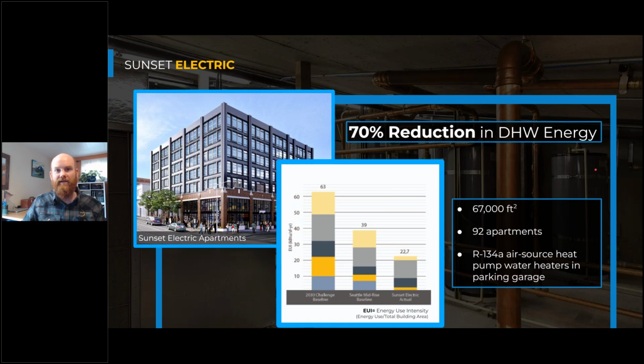And we put it in the parking garage because the R134A refrigerant doesn't perform well under about 40 degrees Fahrenheit. And in Seattle, it gets cooler than 40 degrees. But if you put it in an enclosed underground parking garage, we're creating a buffer zone for that air. And so that air, even when it's drawn into that garage at about 23 degrees on a cold day in Seattle, by the time it gets down to the basement level of the parking garage, the air is warm enough for those heat pump water heaters to extract the heat out of it. It's above that 40-degree threshold. We're getting a lot of great geothermal ground contact with those concrete walls that are uninsulated. There's a lot of thermal mass down there. So it's a really simple but effective way to utilize a technology that's limited by the air temperature in an area which has a few extreme days of low temperatures.